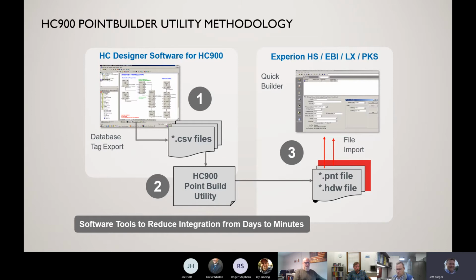Point Builder utility is another thing that offers very quick configuration. If you're using a SCADA software like SpecView or Experion, HS, EBI, LX, any of the SCADA packages that Honeywell might have, what this allows you to do is once you've built your configuration into the HC900, there's an export tool, so it exports all of the data tags to a CSV file, and then later on you can import that into the Honeywell SCADA system, allowing you to build all the points very quickly without having to go through all the individual data tags and rebuilding them. Again, this saves a lot of time in engineering.